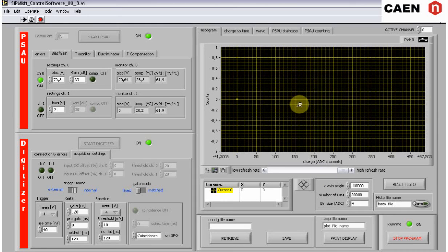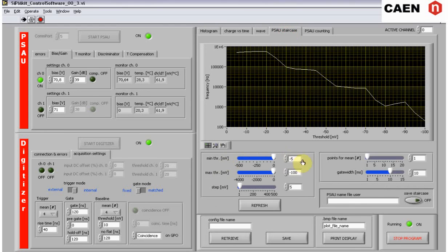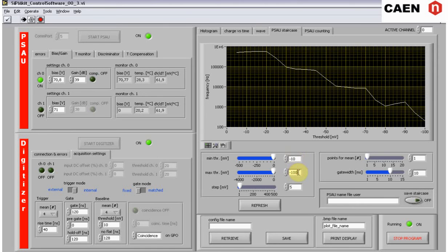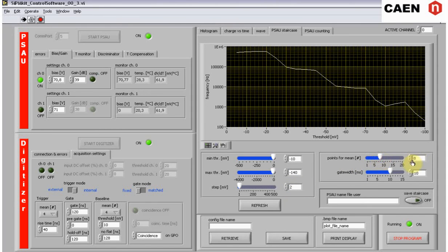To measure it with the kit, select the staircase tab in the graphical section. The staircase allows to scan the rate of the SIPM signals which are over a certain threshold. The graphical user interface allows you to change the starting and final values of the threshold, the step, the number of acquired points for each threshold value, and the gate time for the counting.